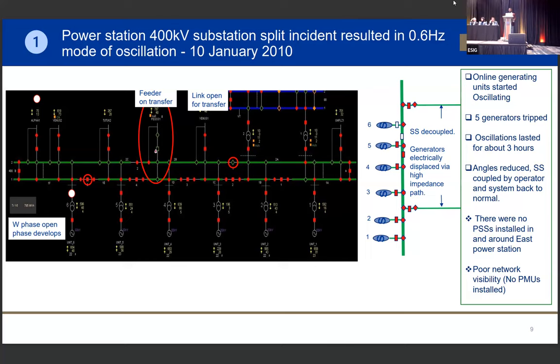It took about 3 hours, but what we did to normalize the system: we tried to couple the bus section to close, but it couldn't close. Then we took the units that were on AGC, automatic generation control, so that they don't cause oscillations. We stopped the unit that came back from outage from loading up. We allowed unit 6 on the other side to synchronize. By doing that, the angle became smaller, and we managed to close or couple the substation.